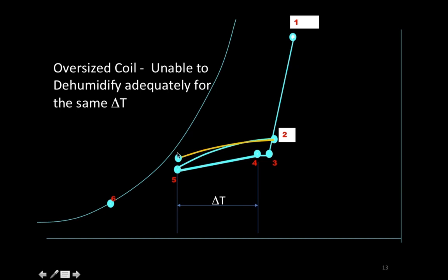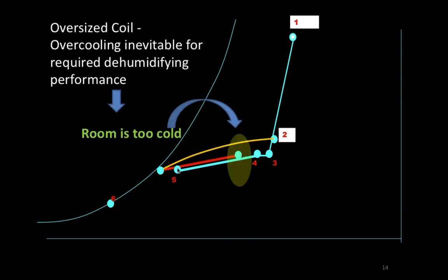You tend to see that temperature is achieved, but the humidity is not. It tends to go a little higher because, as I said, the 2 to this new color that you see here, the yellow color, is the new compatible slope of the coil, but then it is occurring at a different humidity level. So the consequence of that is the space is going to be slightly humid. If we say that we're going to get the right humidity, which means that we have to be at the same dew point as the 5, then we tend to overcool it.